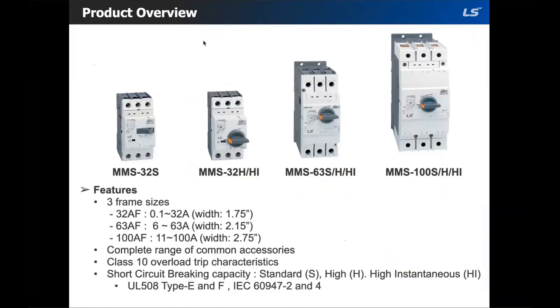In addition to Class 10 adjustable bimetal overload, the MMS also includes a fixed magnetic short circuit trip mechanism designed to trip at 13 times the maximum current rating. We have a standard model indicated with an S, H is the higher breaking capacity model, and HI would be the high instantaneous model which only has the magnetic trip at 13 times the max current.